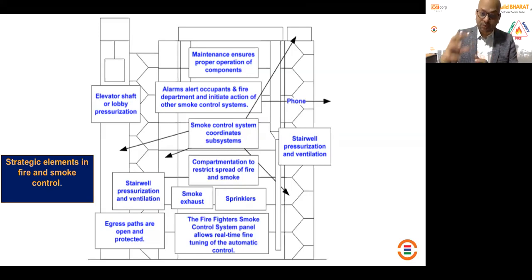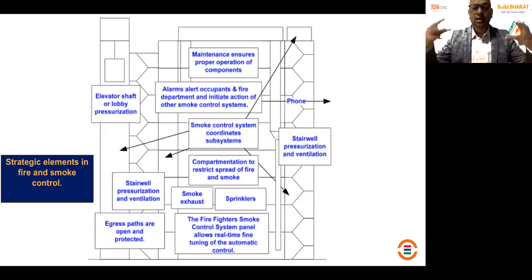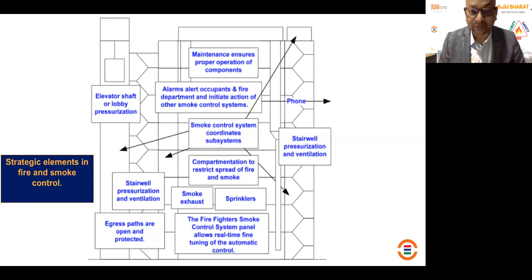Then you have smoke exhaust on top of it inside the building area. It depends on the zoning that you do. Suppose you have a high-rise building, you create that zone in a way that the smoke from the third floor will not travel to the fourth or fifth level. So we are creating horizontal zones. How are we going to create a zone? You create it by applying exhaust fans and smoke dampers. So in case smoke happens, it gets automatically routed through the shaft and goes outside the building. It is not going into the building.